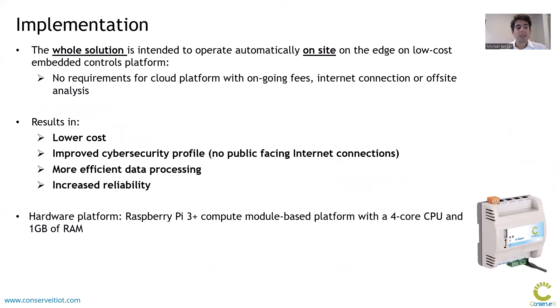The approach was then implemented with the intent to operate automatically on-site, on the edge, on a low-cost embedded controls platform in real time. The advantage is that there is no requirement for a cloud platform, which would have ongoing maintenance fees, require internet connection, and off-site analysis. This results in lower cost, improved cybersecurity profile, more efficient data processing, and increased reliability. The hardware platform used is a Raspberry Pi 3 Plus compute module-based platform with a four-core CPU and only one gigabyte of RAM — a relatively low-powered, low-cost option that can be deployed on site.